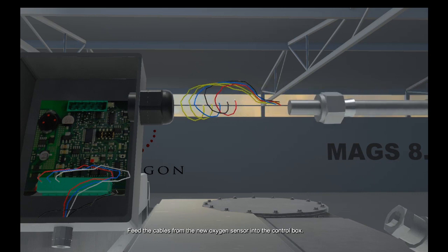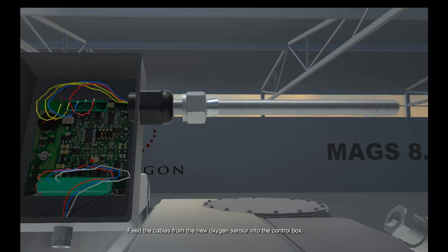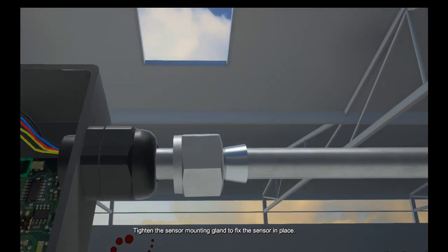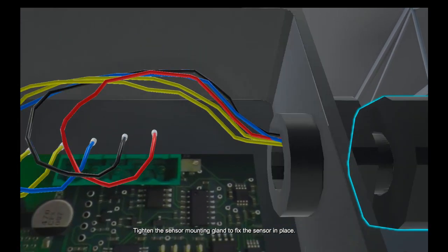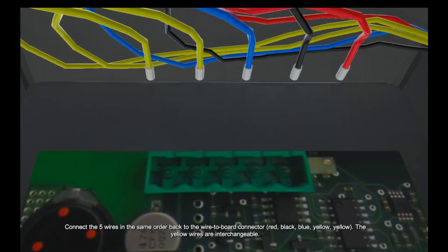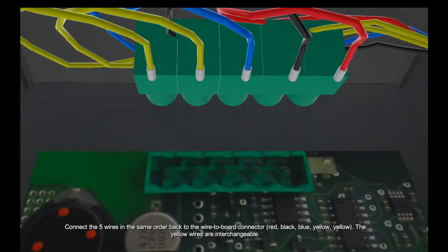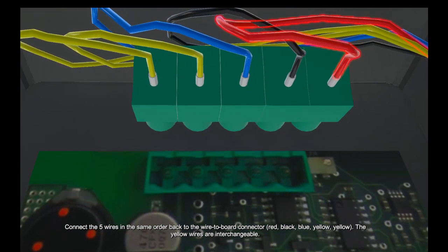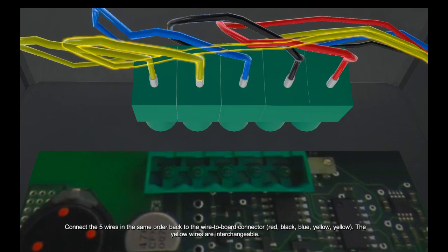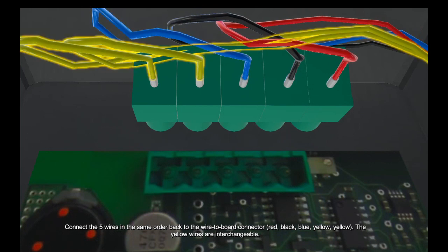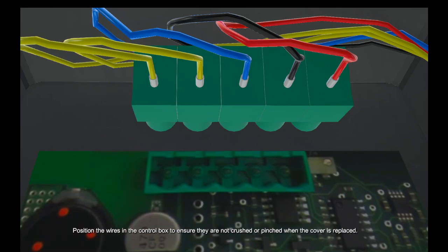Feed the cables from the new oxygen sensor into the control box. Tighten the sensor mounting gland to fix the sensor in place. Connect the 5 wires in the same order back to the wire-to-board connector: red, black, blue, yellow, yellow. The yellow wires are interchangeable.